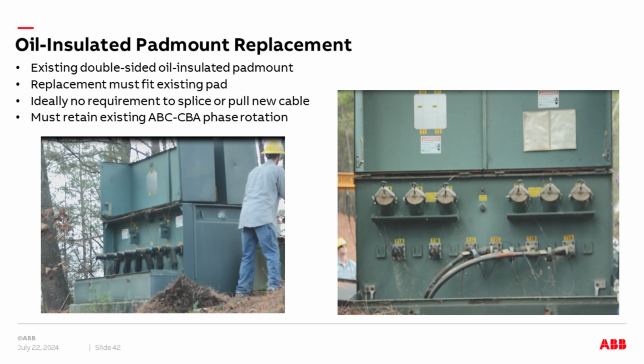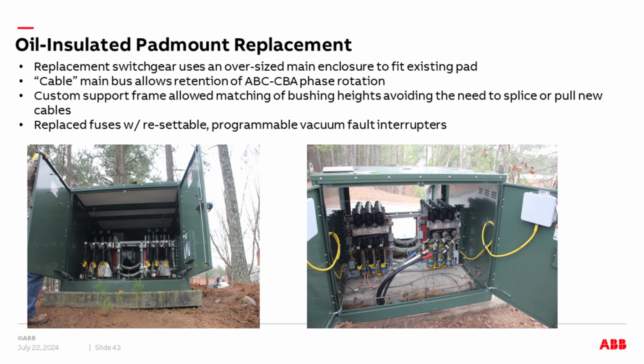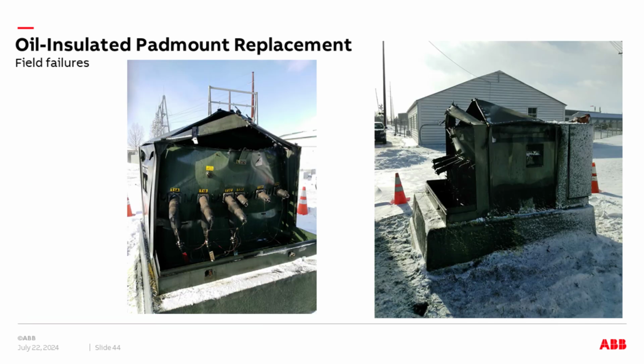This is a particular piece of gear that the customer wanted to replace. Again, it was an ABC to CBA phase requirement to maintain, no new cable, and it had to fit the existing pad. So when this unit was pulled off, you can see here, well, I don't know if you can see it, there's some cable bus across the middle here from the left way to the right way. So it allowed us to make that phase jump from ABC to CBA. We had to build a custom support frame to get the bushing heights to end up in the right places so that the existing cables could be used as is.